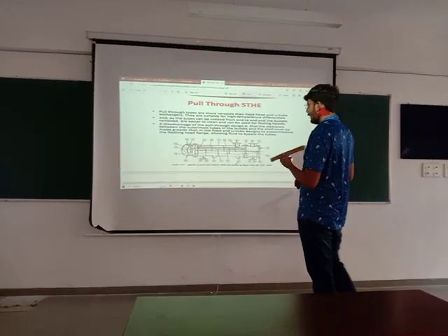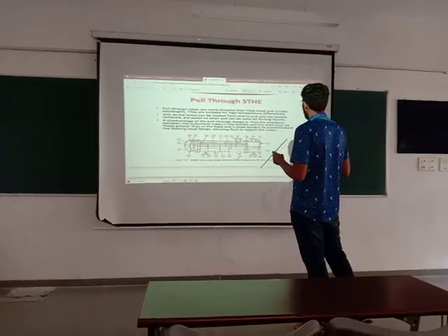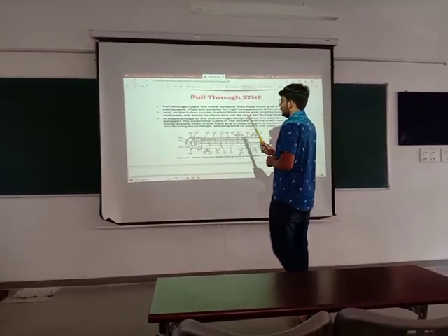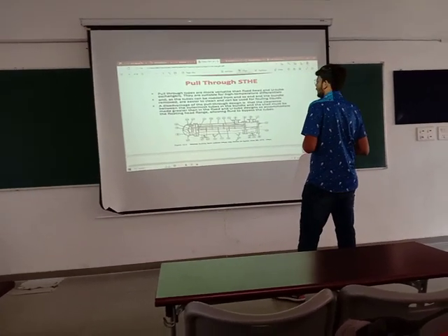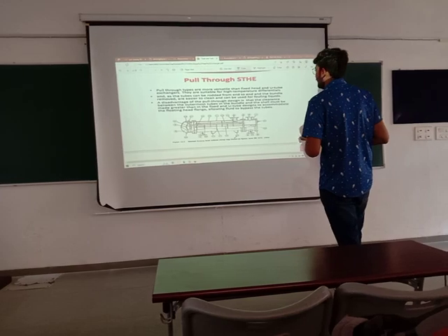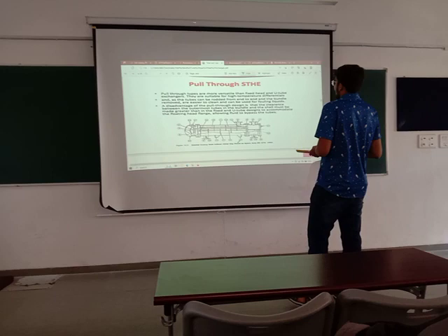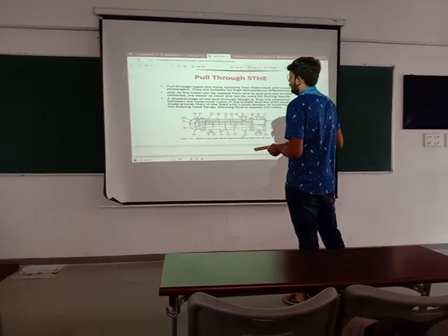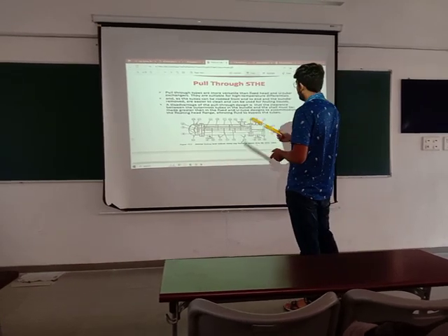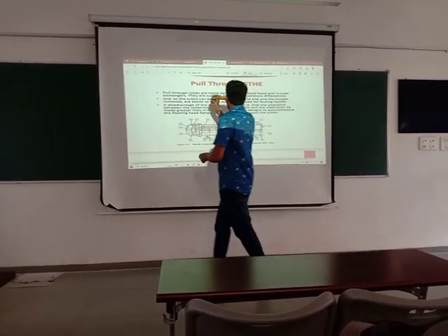A disadvantage of the pull-through design is that the clearance between the outermost tubes and the shell must be made larger than for the fixed head design, to accommodate the floating head flange, allowing the fluid to bypass the tubes. Okay, yes, pull through.